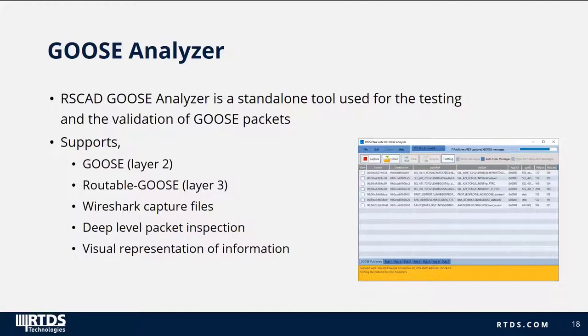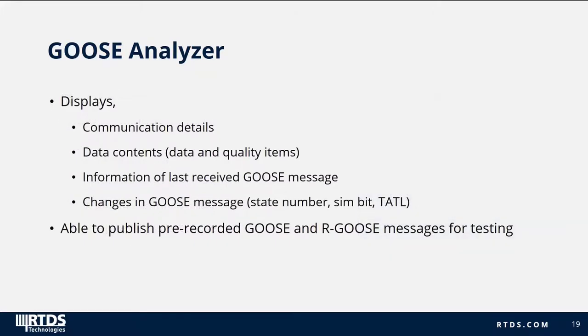Next, I will talk about the GOOSE analyzer. The RSCAD GOOSE analyzer is a software application used for testing and validation of GOOSE packets. It supports both GOOSE and routable GOOSE streams, can open Wireshark captures, provides thorough packet inspection and visual representation of information. You can configure the GOOSE analyzer for a specific application by providing appropriate settings. It displays communication details, data contents including data and quality items, information of the last received GOOSE message, and changes such as state number, simulation bit, and time allowed to live. The GOOSE analyzer is also able to publish pre-recorded GOOSE and routable GOOSE messages for testing purposes.